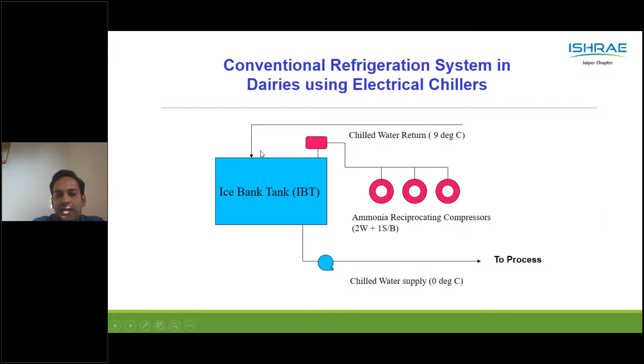In the pharma or dairy sector, mostly in dairies, there is conventionally an ice bank tank, which is connected to normal ammonia reciprocating compressors. In the process, 9 degree water comes in and is converted to 0 degree. In existing dairies, ammonia chillers are installed, and there is a problem of taking electrical power supply from a feeder. There we can use vapor absorption machines in cascade to ammonia.